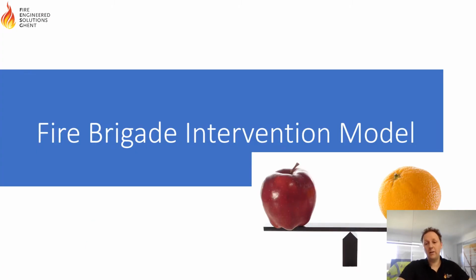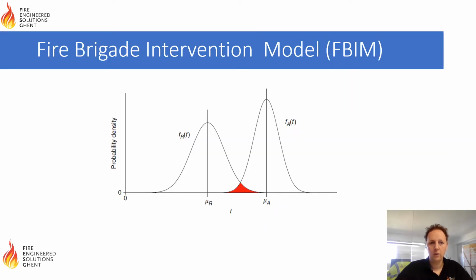Now, in order to compare the different safety measures or to compare the safety levels of a car park equipped with a smoke control system or a sprinkler, we need to step away from the standards and look at a risk-based framework. So we decided to apply the fire brigade intervention model to this problem. The fire brigade intervention model is basically comparing 2 times, as we would do in an ASET-RSET calculation for life safety, where we would say everybody needs to be evacuated before you have untenable conditions. Here we would say the same. The fire brigade would need to be able to intervene before the fire has become too large. So we basically compare 2 times.